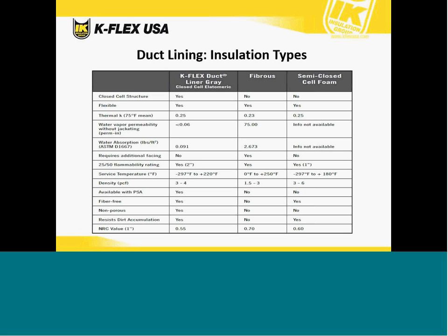Here we are comparing some duct lining insulation types, K-Flex duct liner gray, fibrous duct liner, and semi-closed cell foams, with the standard metrics. Again, it discusses things such as your thermal K, your water vapor permeability, your flammability ratings, your density, and so forth. They're good charts here.